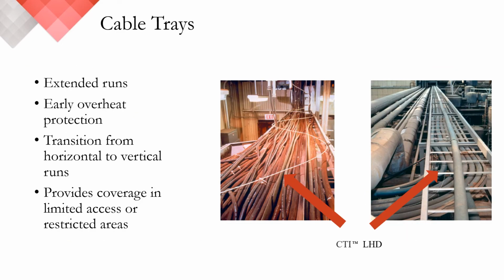Within the power industry alone, we can point to nearly a dozen different areas where linear heat is actively used. In cable trays, which can be applied in just about every commercial or industrial facility, we see linear heat providing early detection for overheating of primary cables. These are typically large, heavy gauge copper conductors carrying extreme electrical loads. Overheating and fire are both very real concerns, and in this example, linear heat is traversed above and in some cases in direct contact with the potential hazard. In the event of a fire, having detection capabilities this close to the hazard enhances your early warning system.